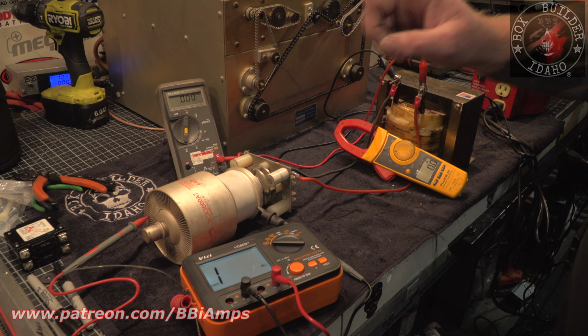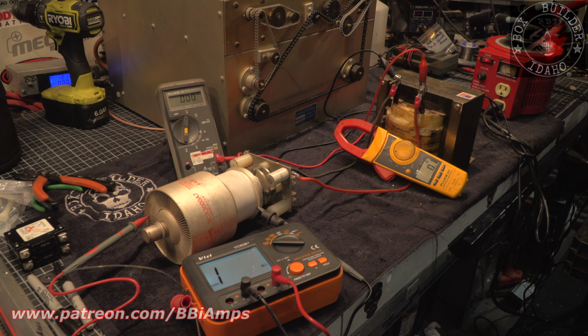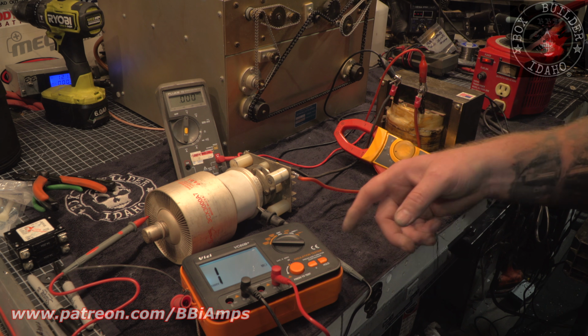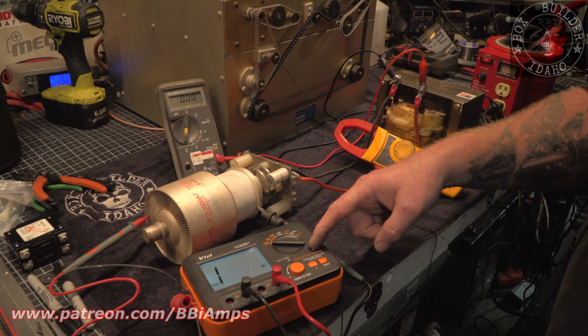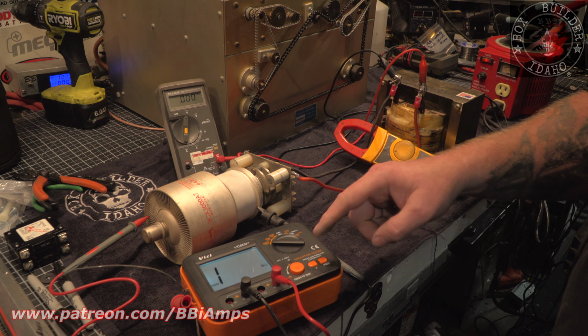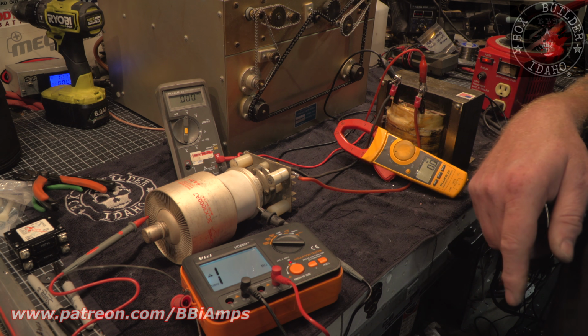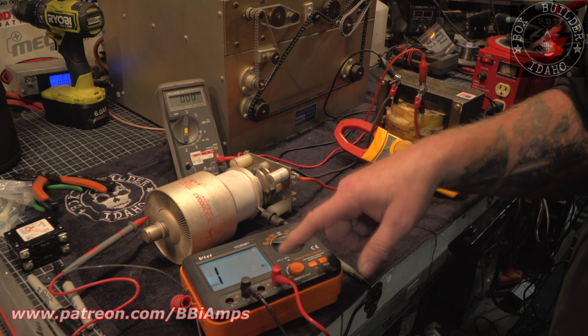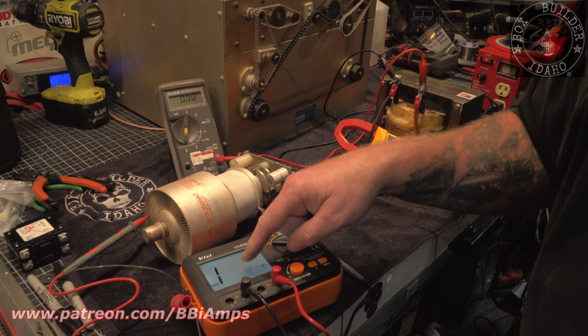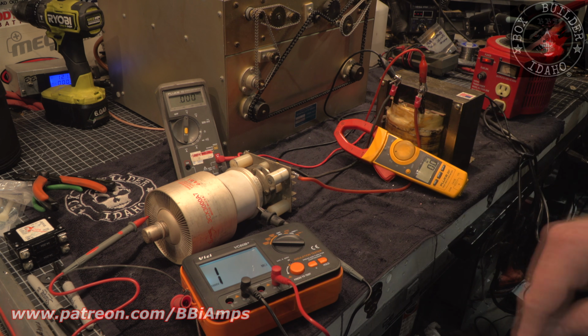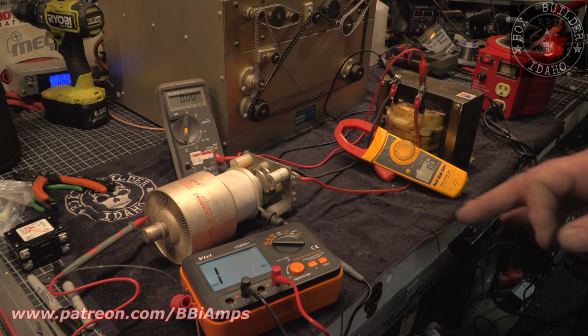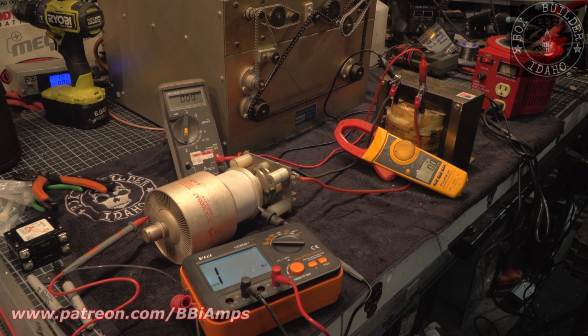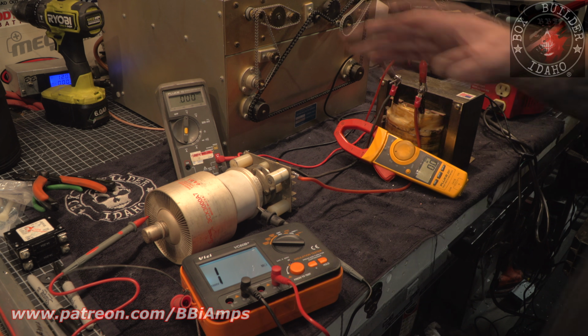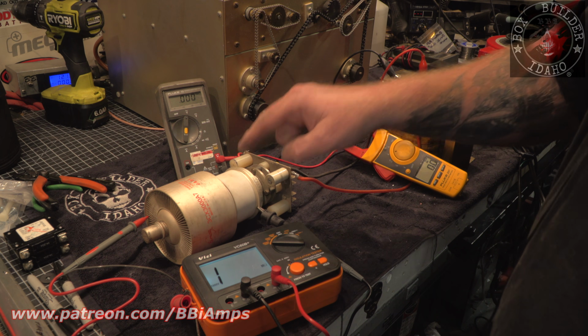This is our amp clamp, and this is a meg meter that'll allow me to test the insulation value of this tube up to 1,000 volts by pressing that button. If we see anything other than 1 on that meter, we have a leak. This will not tell us grid emissions of the tube, it's not going to tell us output potential, none of that. The only thing I'm looking at is to make sure the seal for the tube is still intact.